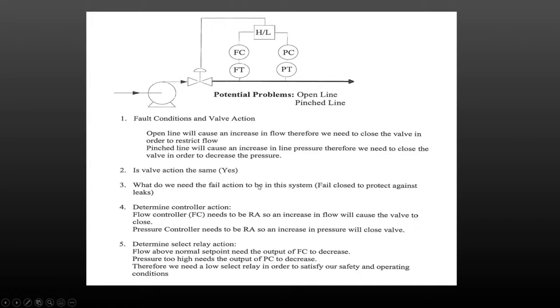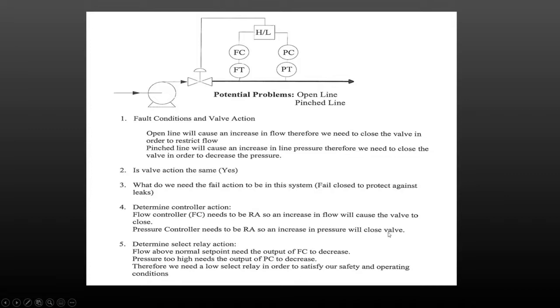Then we determine the controller action. The flow controller is going to be reverse acting — with an open line the flow increases, sending an increasing signal into the controller. This is a fail closed valve, so with an increasing signal it would open; we don't want that, we want it to close, so the controller must be reverse acting. The pressure controller also needs to be reverse acting so that an increase in pressure closes the valve — an increasing signal in must produce a decreasing signal out.